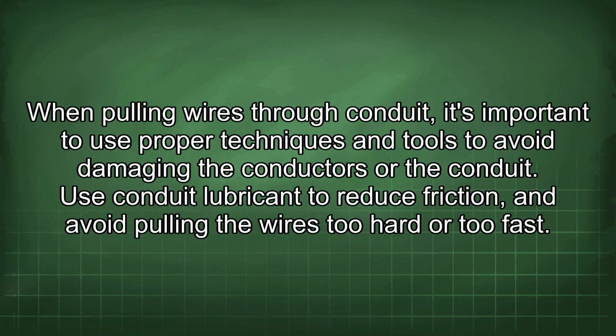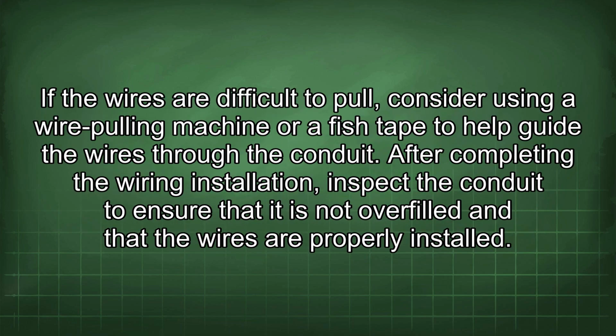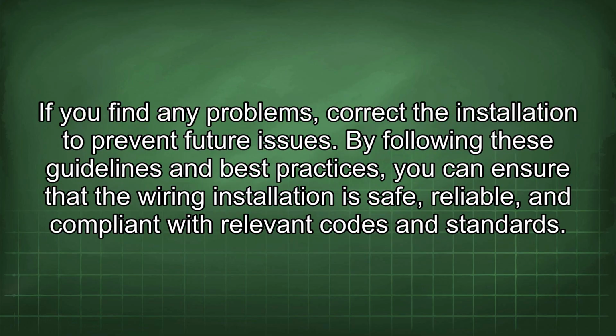When pulling wires through a conduit, it's important to use proper techniques and tools to avoid damaging the conductors or the conduit. Use conduit lubricant to reduce friction and avoid pulling the wires too hard or too fast. If the wires are difficult to pull, consider using a wire pulling machine or a fish tape to help guide the wires through the conduit. After completing the wiring installation, inspect the conduit to ensure that it is not overfilled and that the wires are properly installed. If you find any problems, correct the installation to prevent future issues.